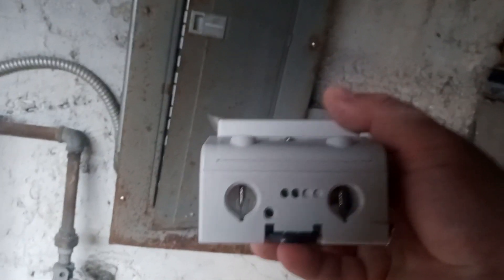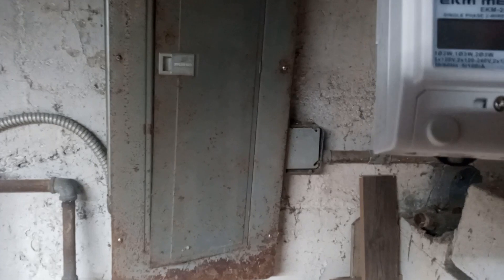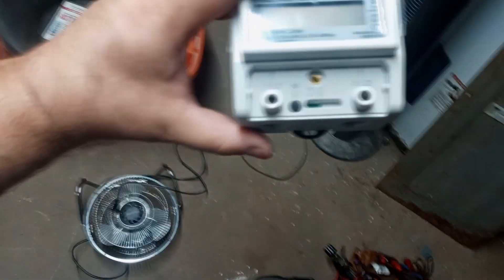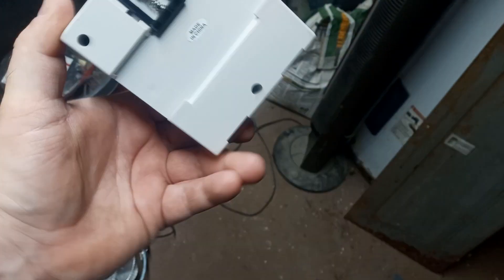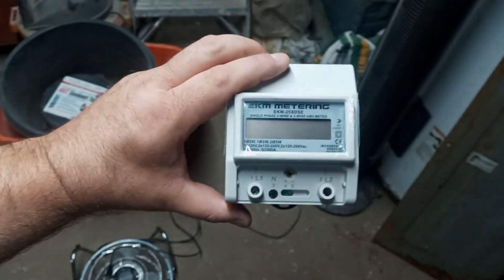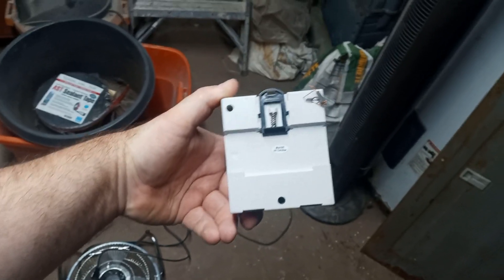I see — two terminals on the bottom. I guess that's where power is applied. So I'm guessing he wants this mounted inside this box. This definitely will be a custom job. I see how this works — yeah, you pass your lines through it, but on the bottom side it's got these screws that go in and puncture the line, so that's where it gets power from. Those two outputs there in the center are for a pulse output — that's an option we're not going to be using. And then you've got your neutral on number three there. The problem is this is not resettable, so I don't know how they're going to reset it once a month. I guess they're just going to take readings. Of course it's going to give you kilowatt hours, and it's probably got a couple different settings for readings. So we're going to mount this thing in that box. It's rail mountable, so this is going to be a complete custom job.